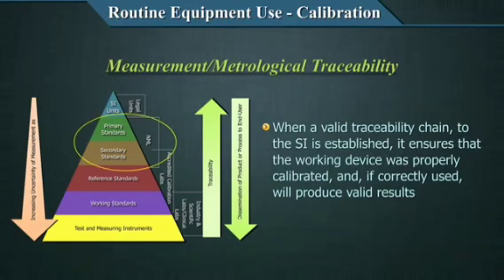Therefore, it is important that an unbroken chain of comparisons is developed as far as practical, keeping in mind the degree of uncertainty of measurement that increases as the chain goes down. The degree of uncertainty must be mentioned on any calibrator or calibration certificate, depending on which the laboratory can decide the acceptability. This unbroken chain of comparisons is called traceability. I hope that concept is clear.